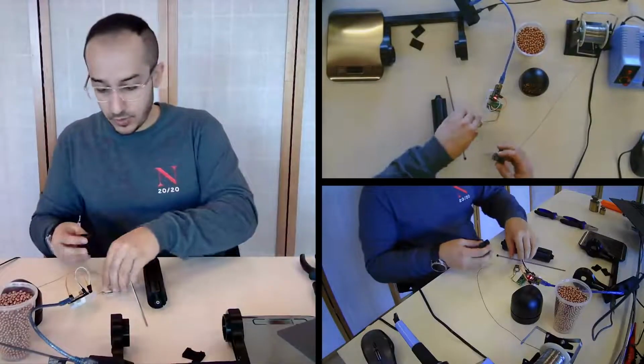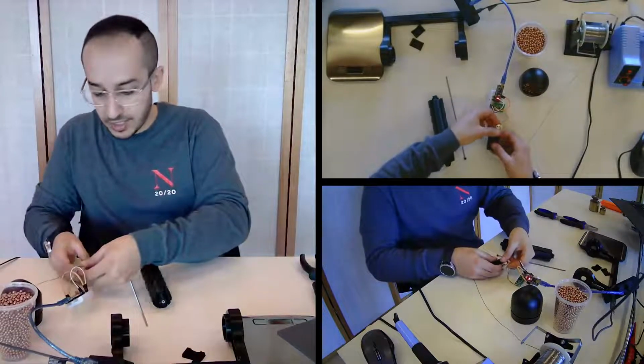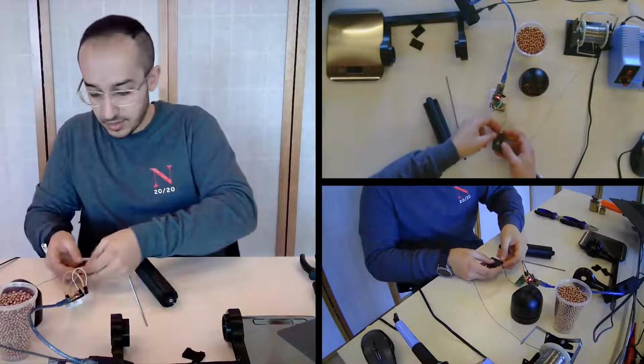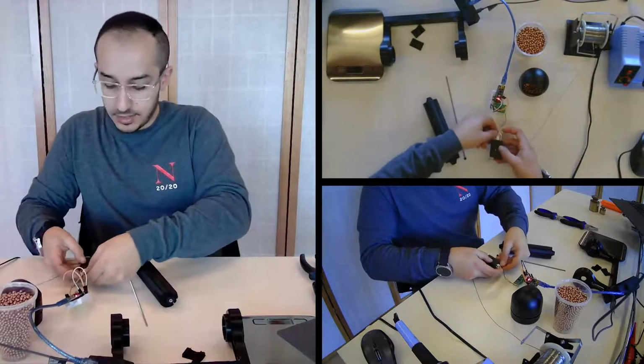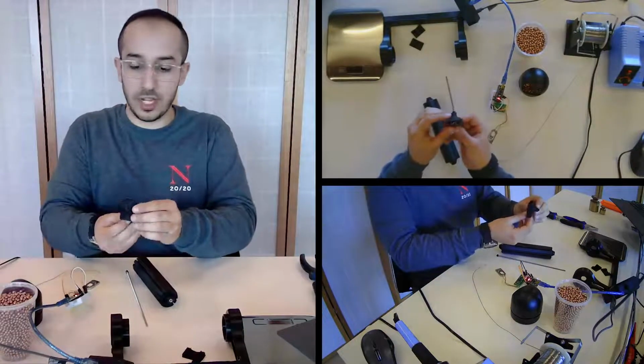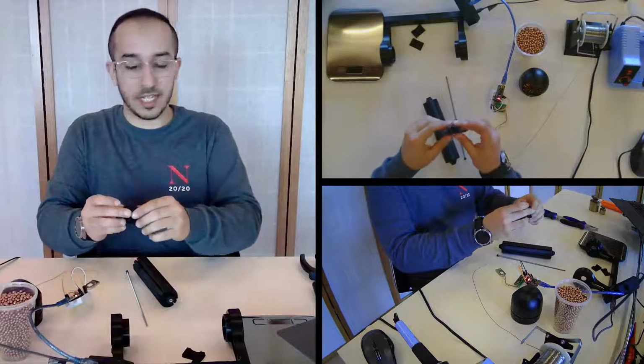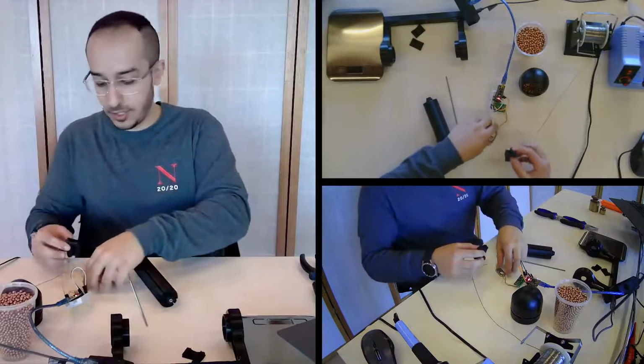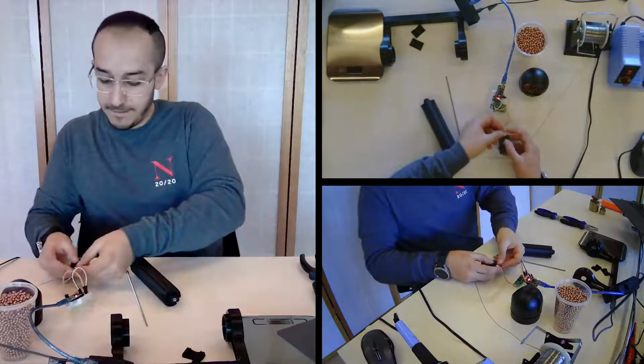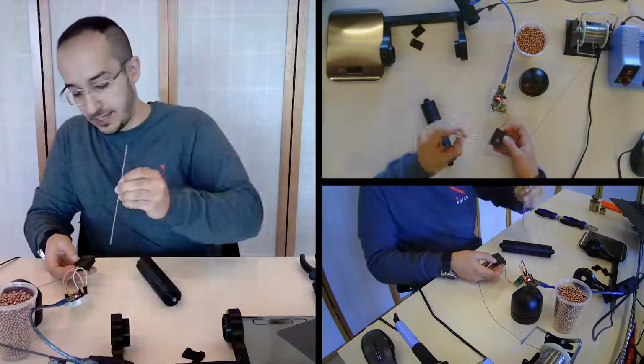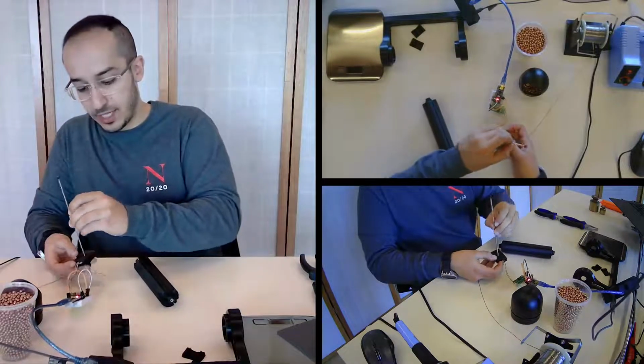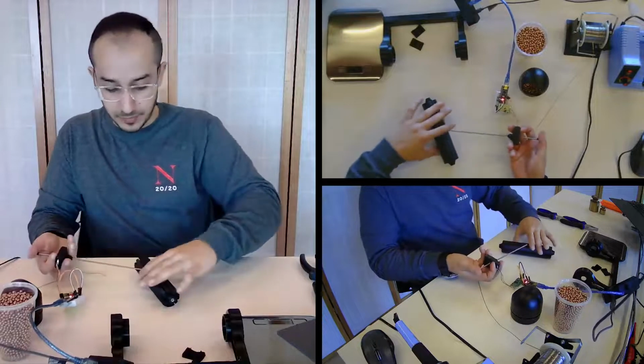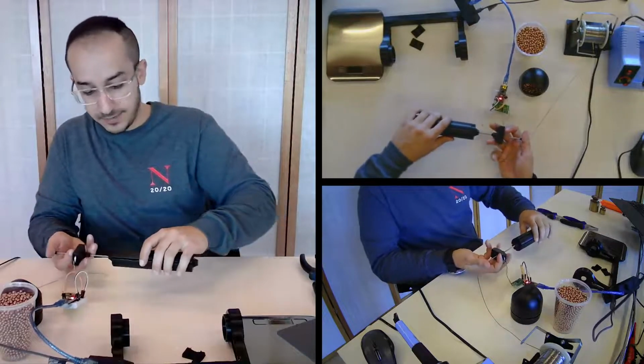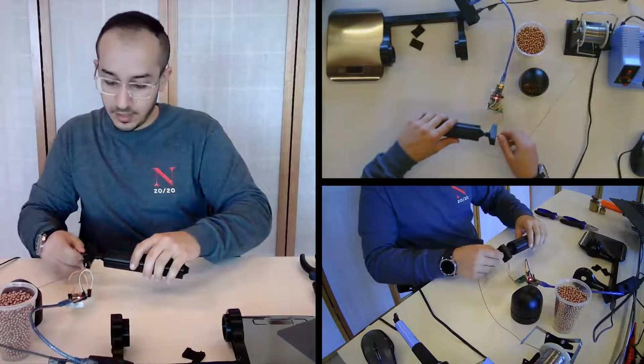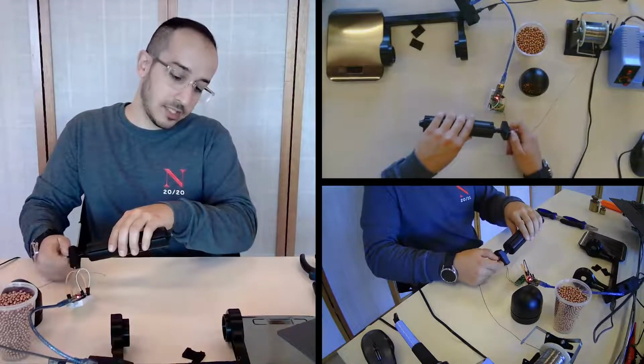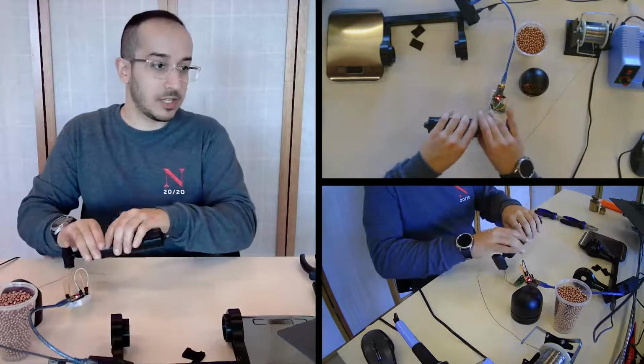Then you are going to put the load cell inside the load cell mount. And just to note that there is two ends to this, you want to feed it through the end that has that extra pocket for the load cell. You pass that through, you pass the threaded rod through the hole of the load cell and through the mount and through the sensor body and thread it so that it's coupled against the nut we placed on this end.